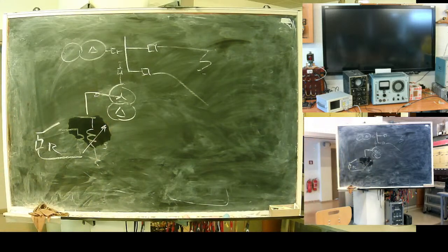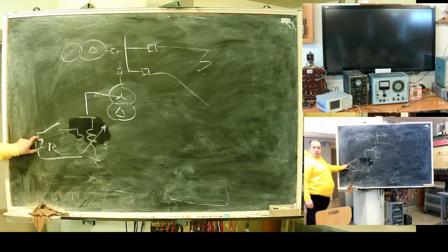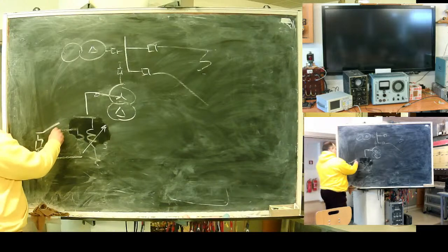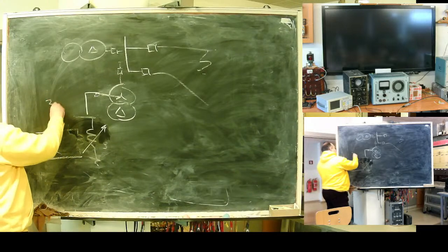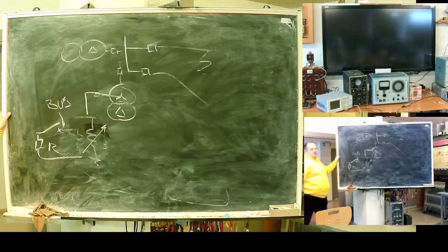Here is what I draw. Compensated neutral with resistance, so it's low ohm neutral. This one switches if the zero sequence voltage is above 1/10 of the direct sequence. Something like this will be sufficient. This thing appears to be complex and a bit expensive.